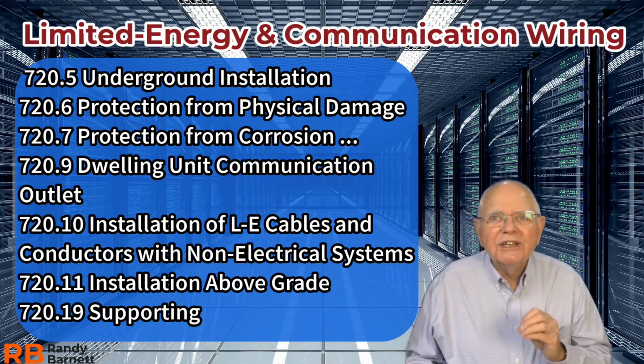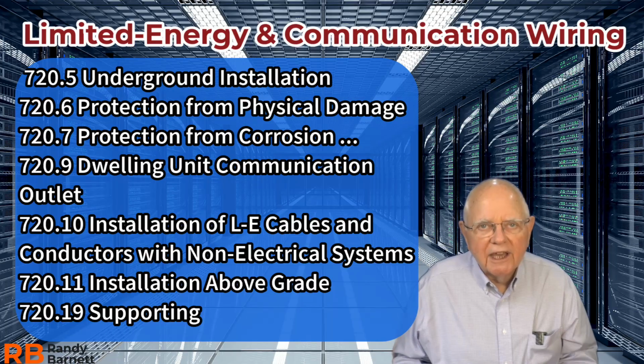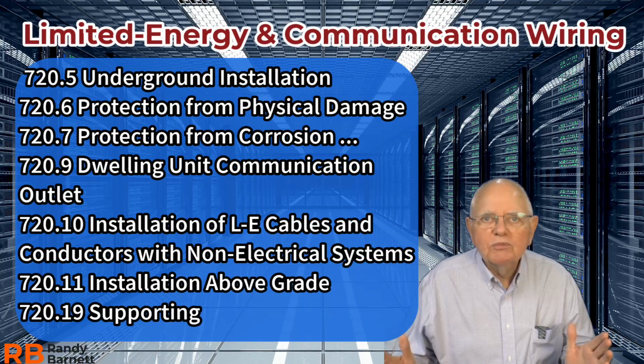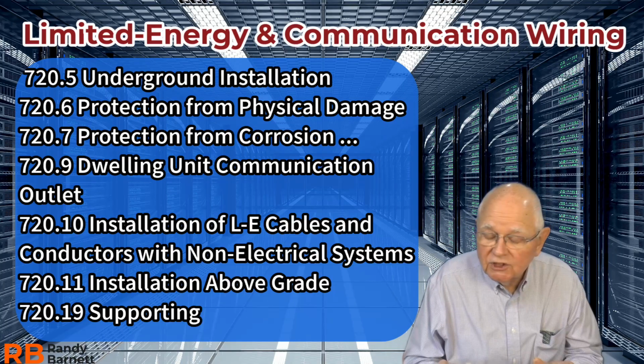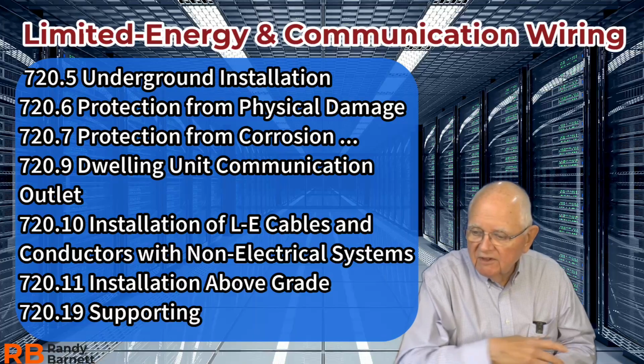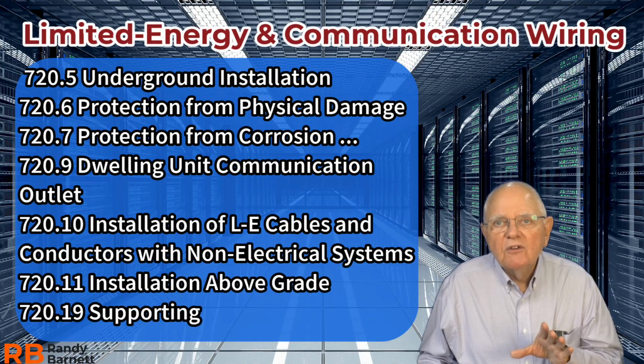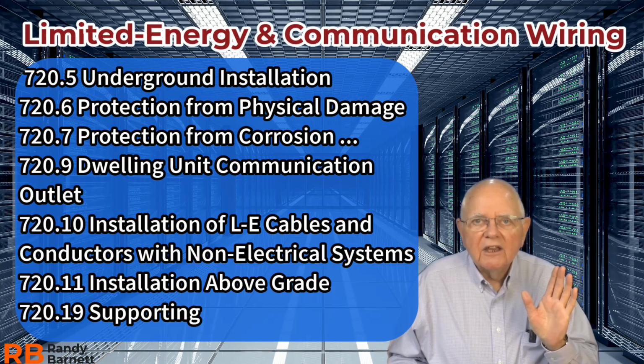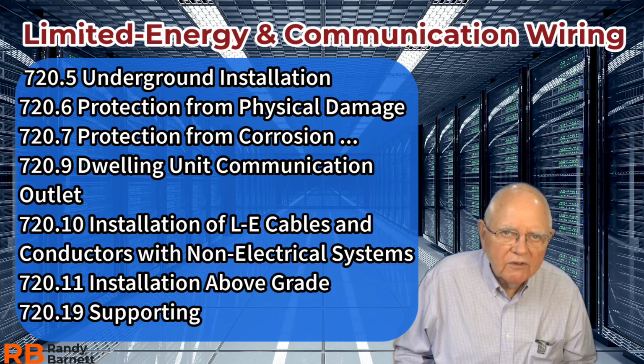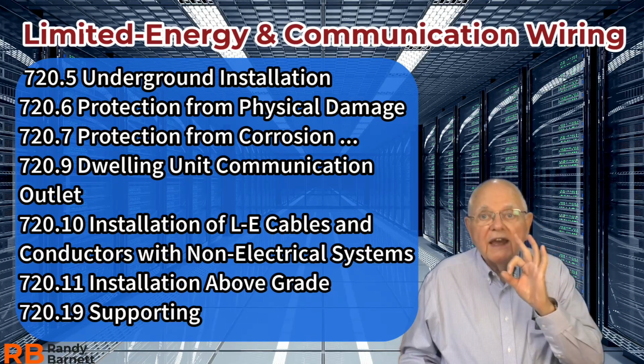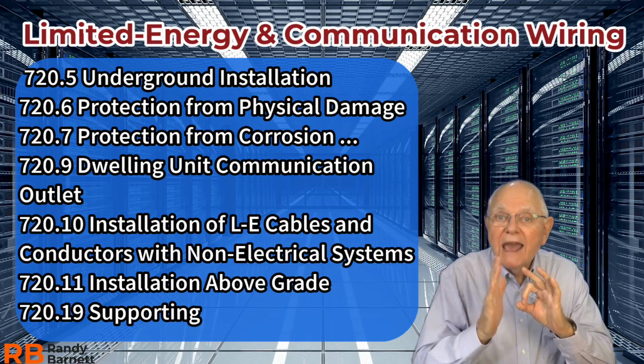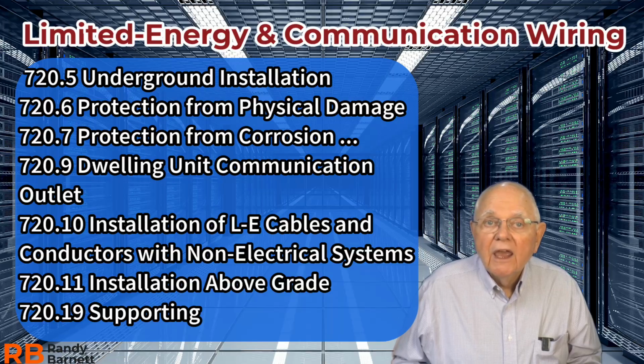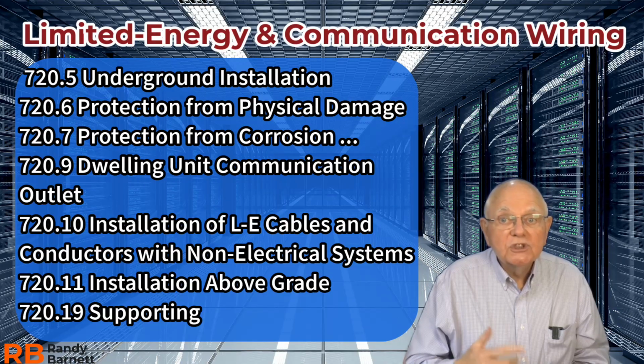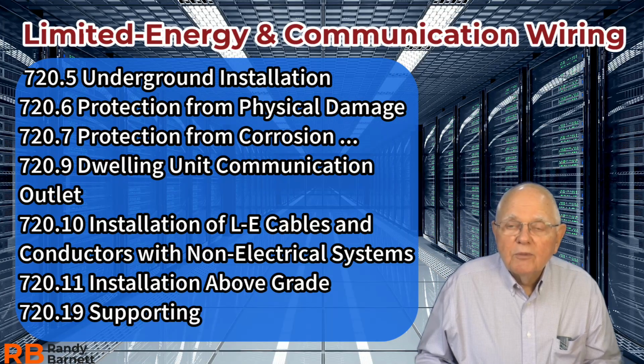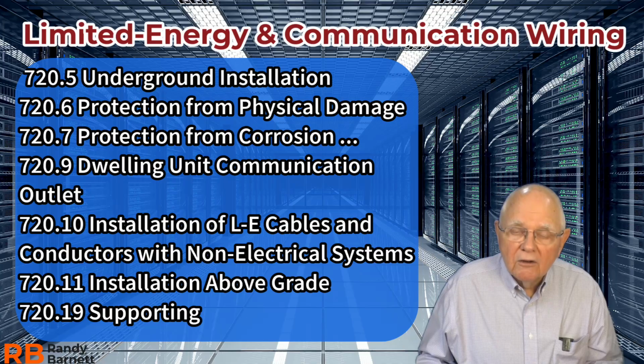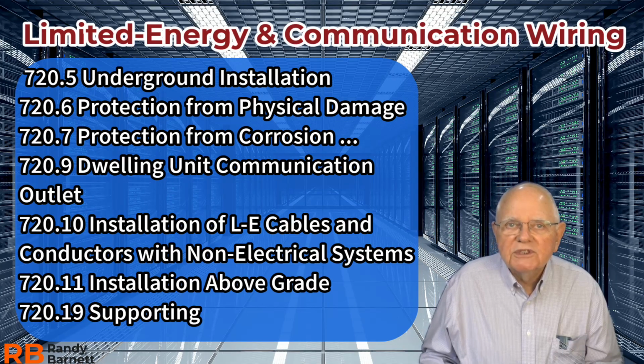720.6 talks about protection against physical damage for my limited energy cables then. General rule, I've got to give them protection, right? I can use any raceway that I use in Chapter 3: rigid, EMT, PVC, whatever, okay? As far as my fill requirements in those raceways, same thing. Go to Chapter 9, Table 1 for my fill requirements. When I go through a wood framing member, the edge of that hole has to be 1¼ inch back from the edge of my framing member then. Or I have to put a steel plate over it. Bushings or grommets are used if I go through a hole when I'm pulling those limited energy cables through metal framing members. Once again, to give them physical protection, right?